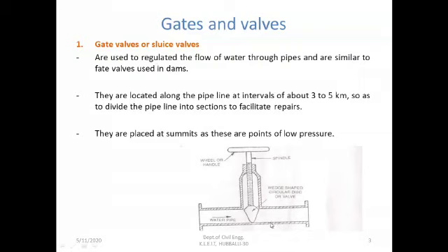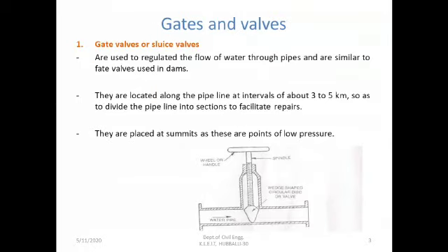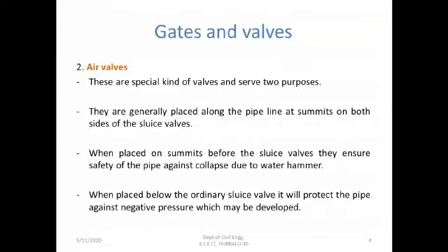And where they are located in the pipelines, it is at intervals of about 3 to 5 kilometers, so as to divide the pipeline into sections to facilitate repairs. Usually they are placed at the summits or at the higher elevated points wherein the pressure is low.